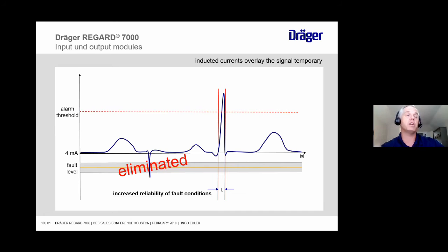And that's some of the problems that traditional controllers have. We basically said, okay, if you see 12 milliamps, Mr. Controller, trip that alarm. Doesn't matter if he sees it for 1 second or 5 seconds or 10 seconds. And what you're seeing is about 1 second it spiked up there. Well, that can't be gas, because like I said, it takes a little bit of time for the transmitter and the sensor to actually read that gas, and once the gas dissipates, to start reading back down to the 4 milliamp value. So with the Regard 7000, with that adjustable alarm suppression time, we can make sure that the sensor is actually in alarm before we trip that alarm contact.